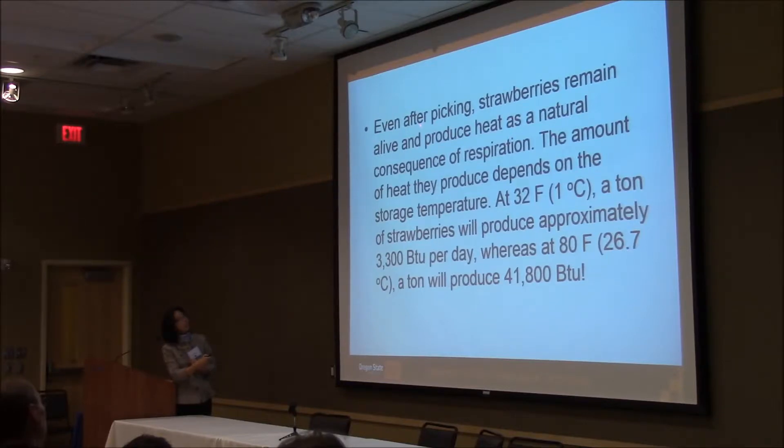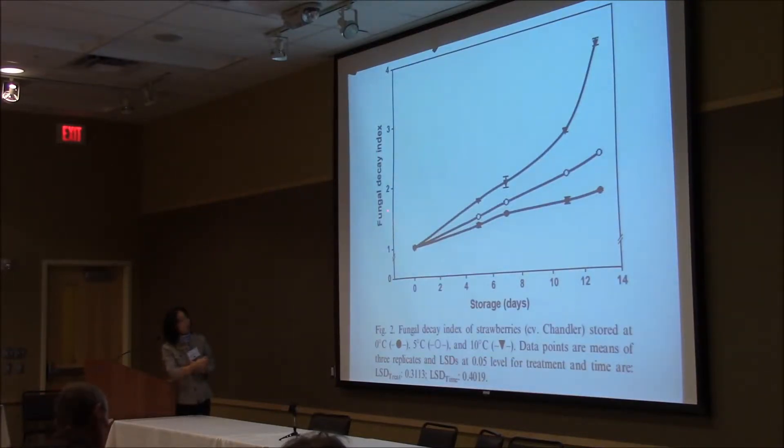Even after picking, strawberries remain alive and produce heat as a natural consequence of respiration. For example, if you store at 1 degree C (32°F), a ton of strawberries produces approximately 3,100 BTU per day. But if moved to room temperature, that's 41,000 BTU — a huge difference. This curve shows how fungal decay happens depending on storage temperature, comparing 0°C, 5°C, and 10°C. You can see how quickly decay happens at higher temperatures, because most organisms just like warm temperatures.